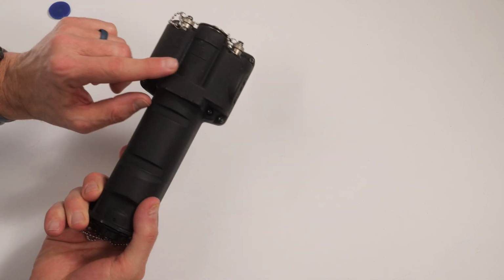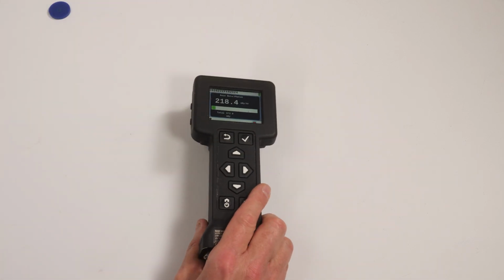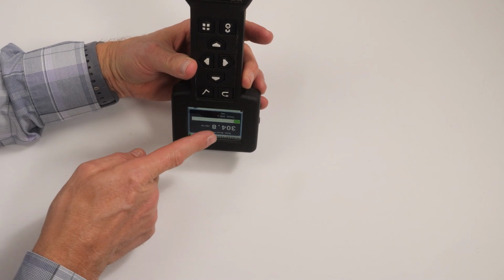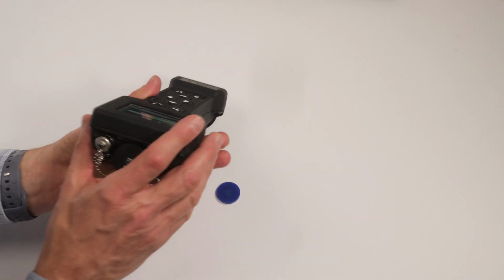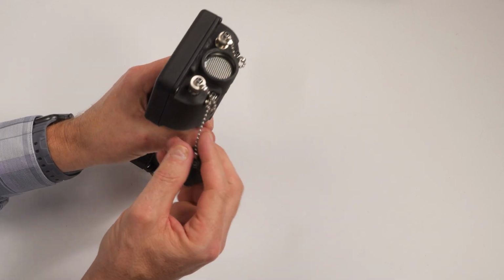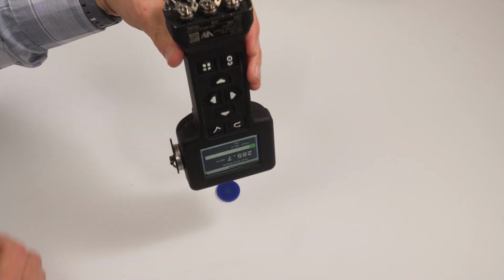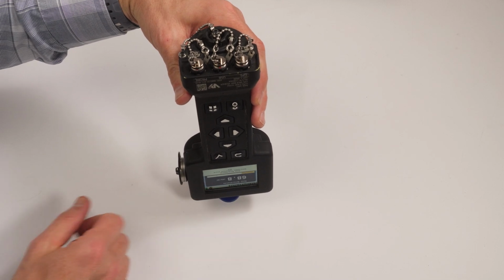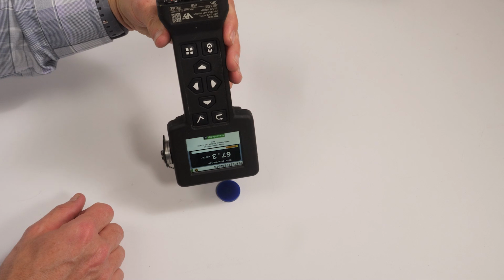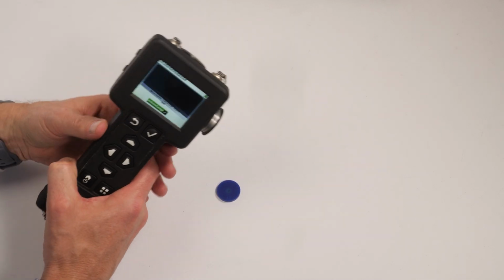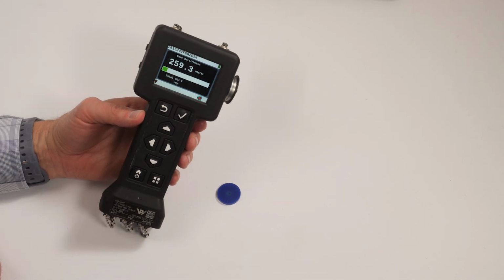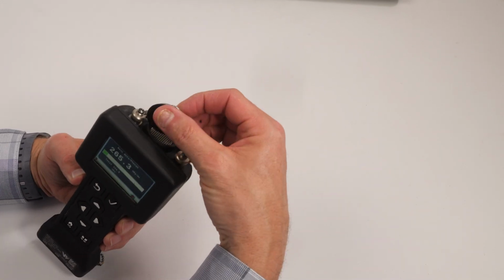When surveying for photon radiation, the base unit's most sensitive spot is on the back of the device behind the screen. The detector crosshairs show these locations. You can use the base unit radiation readings to determine if there is significant amounts of beta radiation on a surface. With the beta window cap installed, orient the base unit perpendicular to the surface. Observe the reading. Remove the beta window cap and place it on the magnetic surface on the right side of the base unit. With the beta window cap removed, orient the base unit perpendicular to the surface, holding it above the suspected area, but not touching it. Observe the reading. If there is a noticeable increase in the radiation reading, it is an indication that beta radiation may be present.